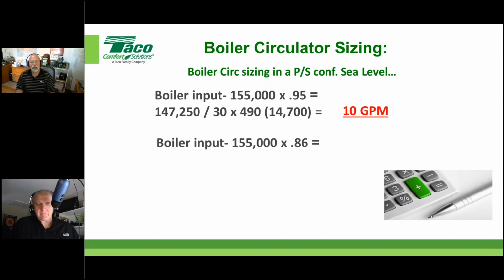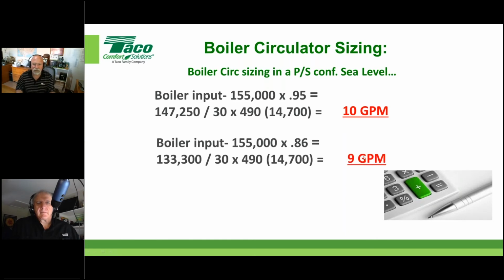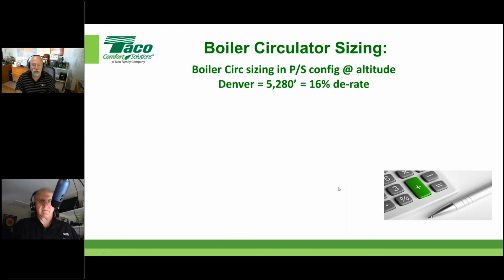Okay, let's take that same application, and let's say that boiler is going to run hot a lot in a non-condensing mode. So we're going to use 0.86. It's the same math, folks. And for the sake of time, you're going to drop 1 GPM. Now the boiler's a 133.3, not a 147,250, right? So that just drops that 1 GPM.